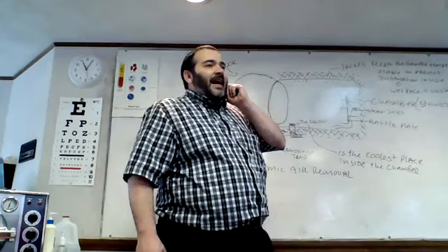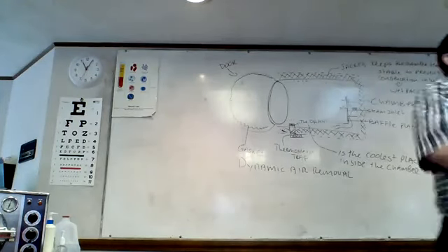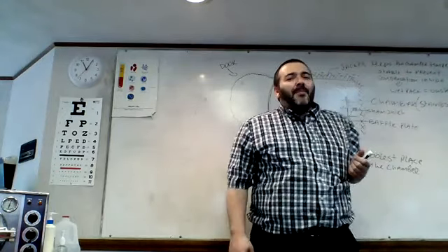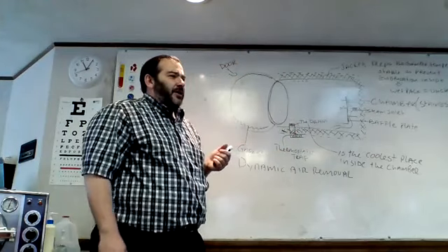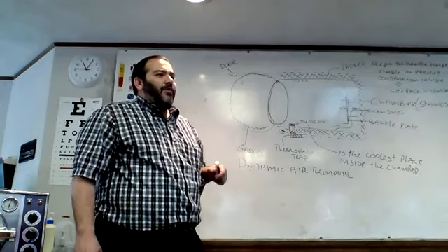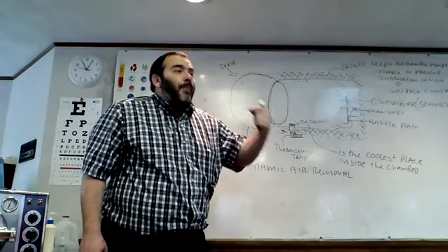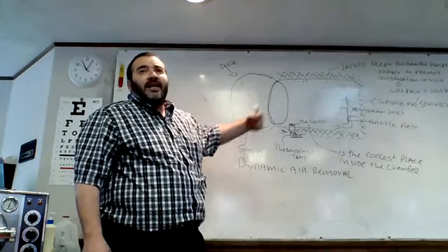See, gravity air removal, or gravity air displacement, is expanding steam pushing out the residual air, right? Dynamic means that we exercise some degree of force or some action to remove the air. So dynamic air removal uses pumps to pump out the air before we inject steam.